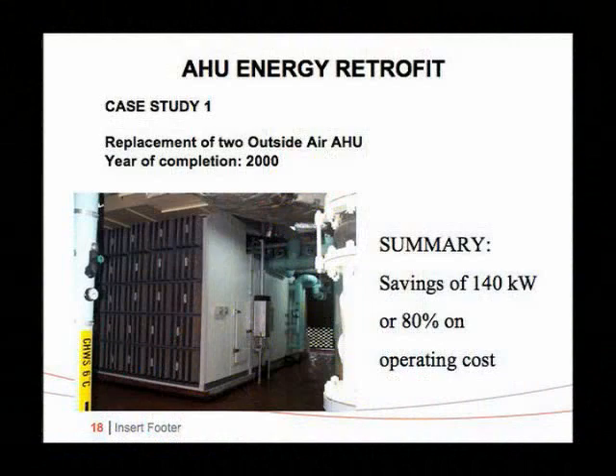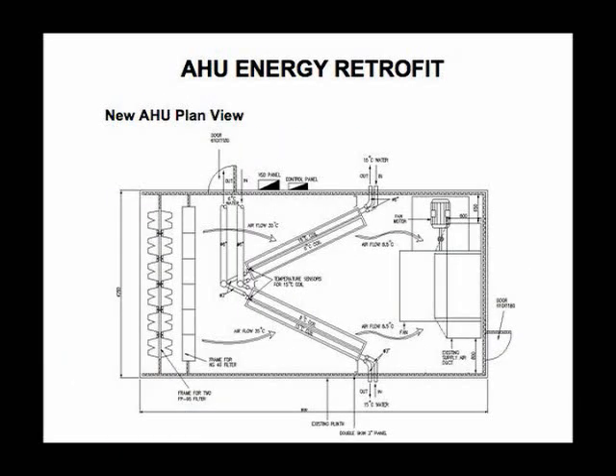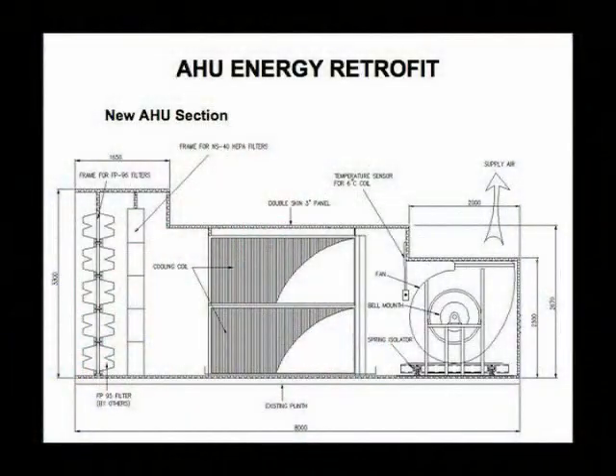So we've tried to apply this. This is for another semiconductor plant in Singapore. Take out the old air handler, put in much higher efficiency filters, and bring the overall CFM per kilowatt up. So in terms of fan and chiller efficiency, 80% reduction. So that's slightly better than factor 4. Plan view, V-shape, the coils to increase surface area, a little bit unusual filter section layout to reduce frictional loss, direct drive on the fan to reduce the rubber losses into the airstream, which are not wanted. Cross-sectional view, so we have to do steps on the site because there are existing cable trays, ductwork, sprinklers, etc., cannot be moved.